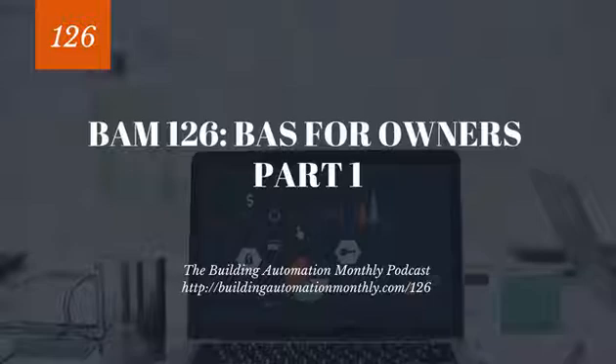Now, in an ideal world, and we'll talk about this when we get to step 4, optimizing the BAS usage, you want to get to a proactive scenario where you're using reporting, analytics, trending, alarming, and you're using all of this to essentially showcase the vital signs of your building systems, so that you can make proactive changes, whether in maintenance, in troubleshooting, or in set point adjustments for optimum performance. But right now, and in a lot of cases, we're going to be just focused on the reactive stuff.